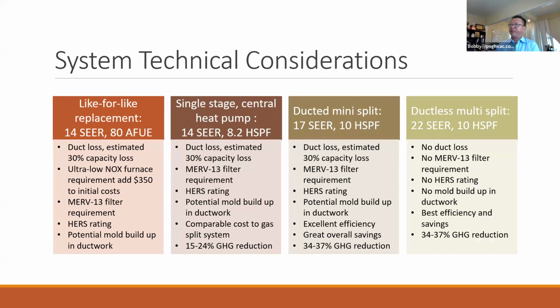And then for our performance option, we have our ductless mini split. We're going to just use an average ductless mini split of 22 SEER, 10 HSPF. However, we don't have that 30% duct capacity loss. We have no MERV 13 requirement. We have no HERS ratings, and the chance for mold in your ductwork is non-existent because there's no ductwork. And best efficiency savings, and in this case, again, we're using a ductless mini split, so we're getting away from gas, up to 37% greenhouse gas reduction.